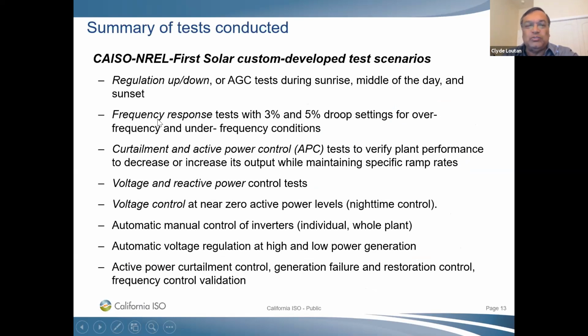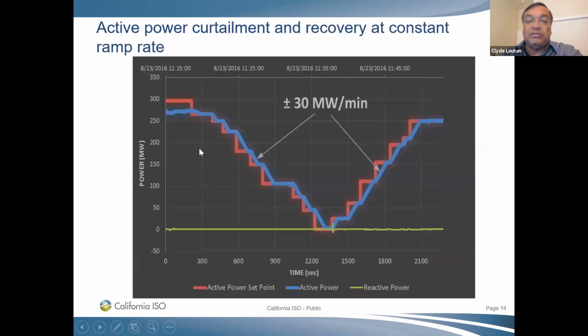We changed the droop settings. We changed the bandwidth settings on the solar plant. We also wanted to see how well this plant could respond to megawatt control from the ISO. And then we looked at voltage control, different types of control, so either a scheduled voltage or megawatt control, or even a power factor control. And then basically how well, under normal steady state condition, can the solar plant react to a dispatch signal from the ISO.